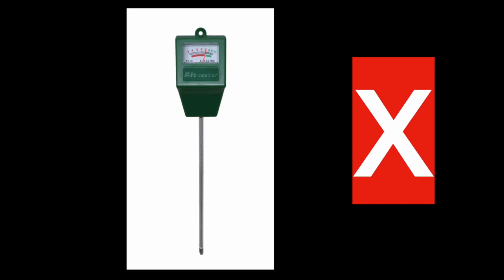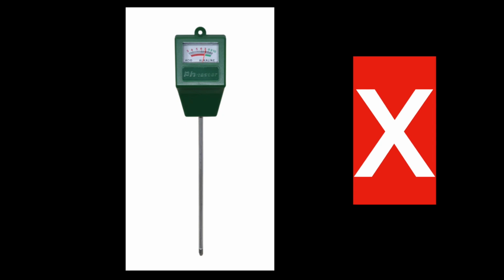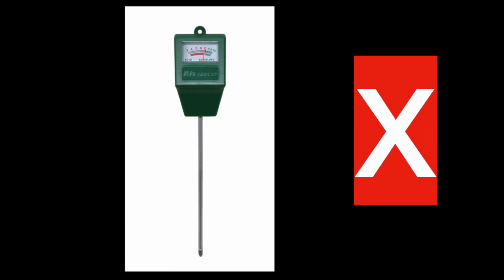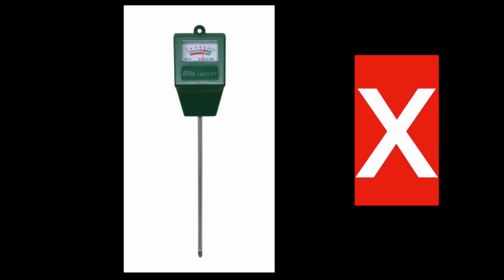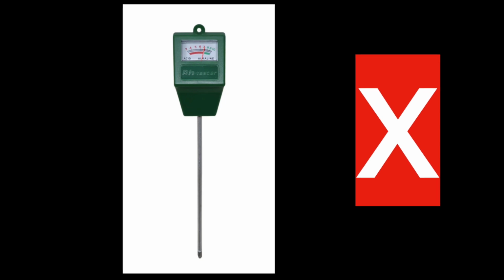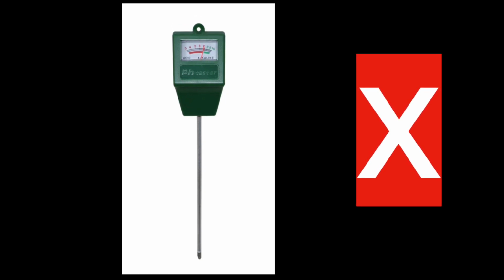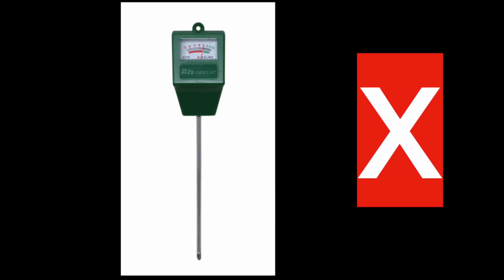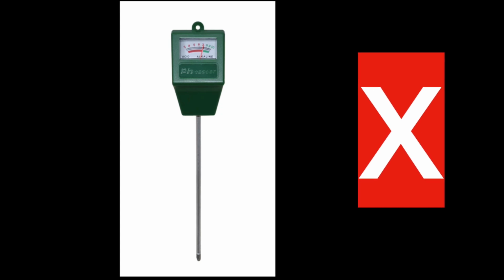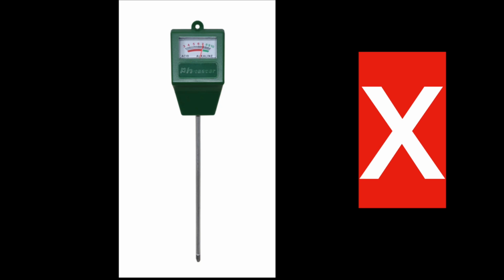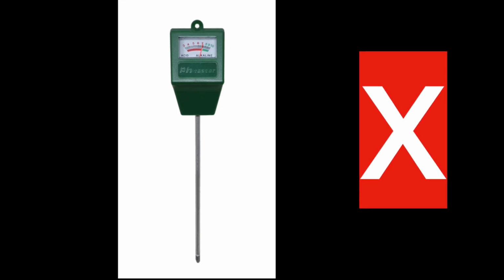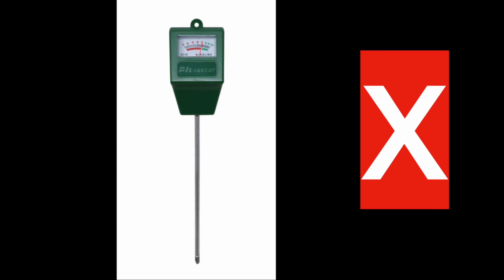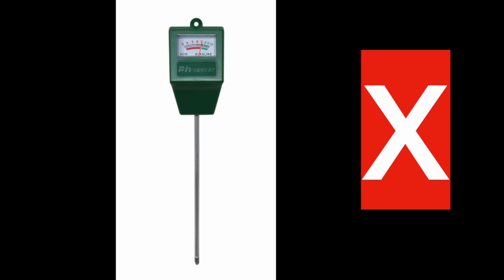And that voltage is influenced by the salt content and the moisture of the soil, which can only be loosely correlated with pH under perfect conditions, but it's not a direct measurement of pH. A dry, salty soil might read as very acidic, while a wet, low-salt soil might read as alkaline, regardless of the actual pH. Okay, so in conclusion, if you need to measure pH in food samples, the best option for you would be to use the standard pH meter and buy a so-called open junction specialized electrode for food samples. Good luck!